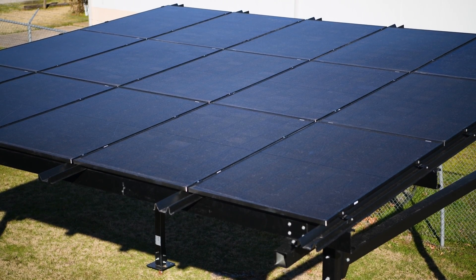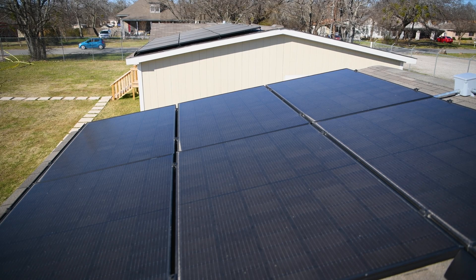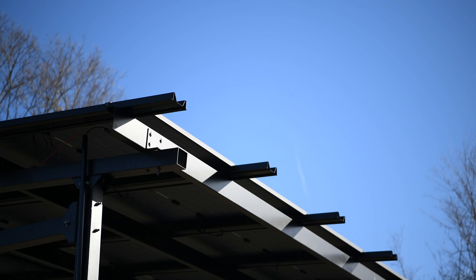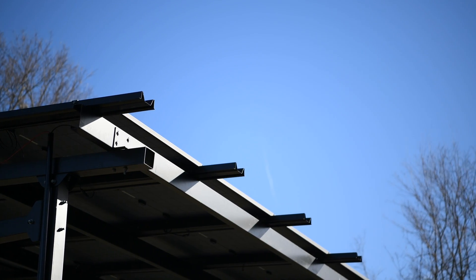To quantify the efficiency of this setup, we will be conducting a comparative analysis. We'll connect this array to our 18K PV system and monitor the solar input from our bifacial panels mounted on the carport, compared to the input from a rooftop array with monofacial panels of similar specifications. In perfect conditions — such as perfect sun capture and concrete or white reflective gravel on the ground — we would anticipate a 10 to 20% boost in power generation, validating the additional cost of this innovative solar solution.